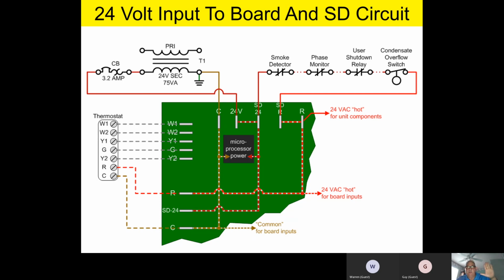You could have a big old fireman switch. You could have a big red button where you hit it and it shuts the unit, whatever you want to do. You could have a condensate overflow switch. The main thing we got to remember, that switch has to be a dry relay output. In other words, it's going to be just a click, click, click, a set of contacts. You don't want to have an electronic sensor, or one of those little time delay relays that are electronic, because that could screw it up. It won't hurt anything or burn anything up, but it may not be reliable.